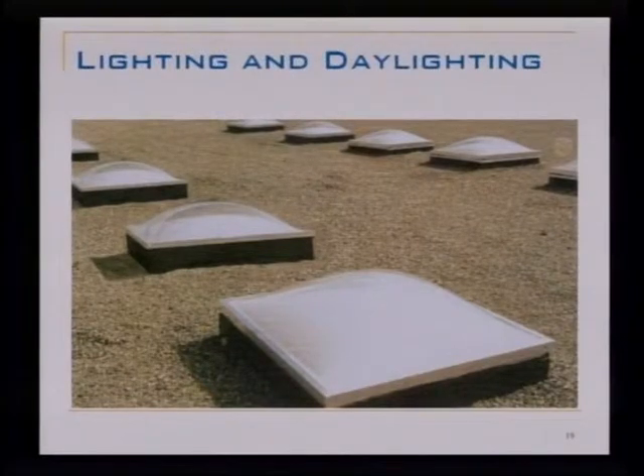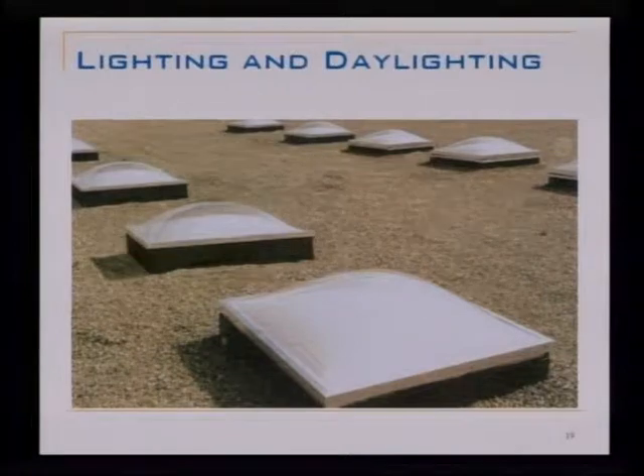Lighting and daylighting is something that has received some attention in grocery store design, but again, when we look to this as an energy efficiency measure, we have to remember that grocery stores are unlike any other commercial building in that they are always in heating. So in most other commercial buildings, if you use less lighting energy, it means you also get to use less cooling energy. Well, in a grocery store, if you use less lighting energy, it means you get to use more heating energy instead. You have to turn your gas furnace on more to make up for the fact that you turned the lights off.